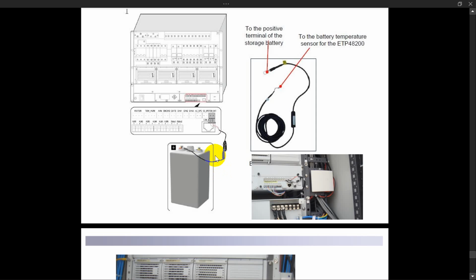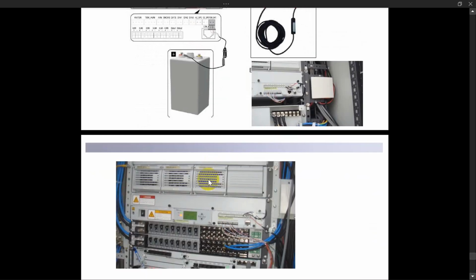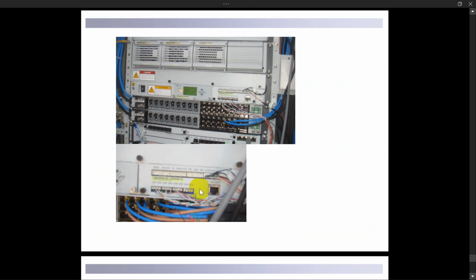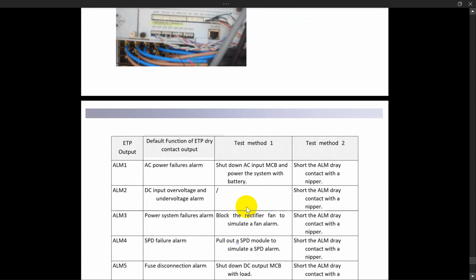In the rectifiers, there is a built-in sensor. As discussed, this built-in sensor takes the battery alarms, battery temperature, and other alarms related to power, and it goes through the rectifier. And from the rectifier, it transfers to the AMU from the same sensor. The same module has input signals coming from alarms, and it also has an output signal going to the AMU. This is how it looks: a cable coming from the battery, like the battery temperature alarm and other alarms, and downside you will find the LAN cable going to the AMU.